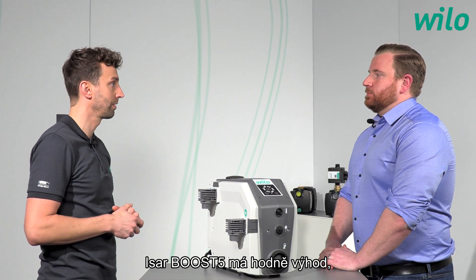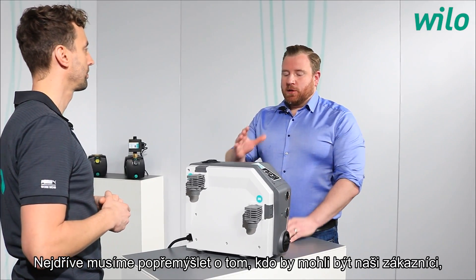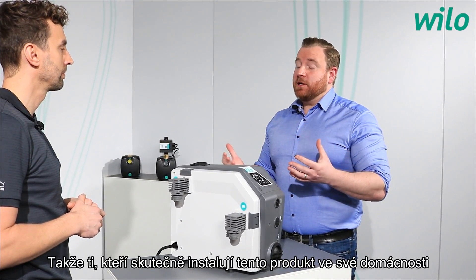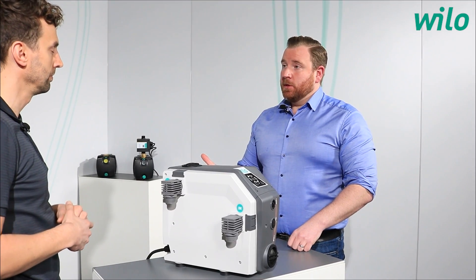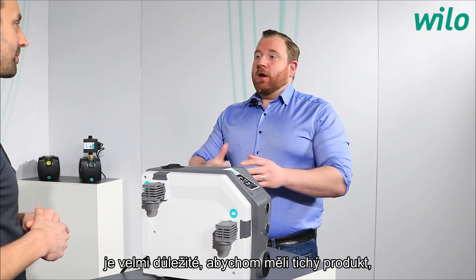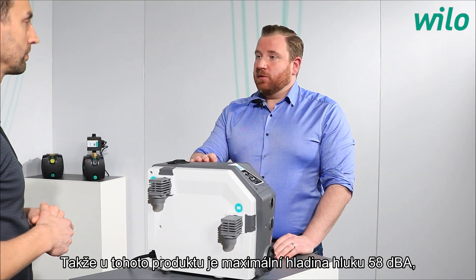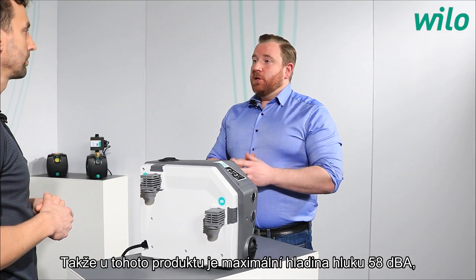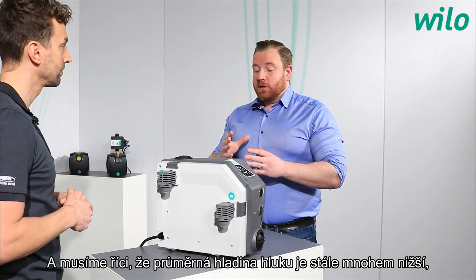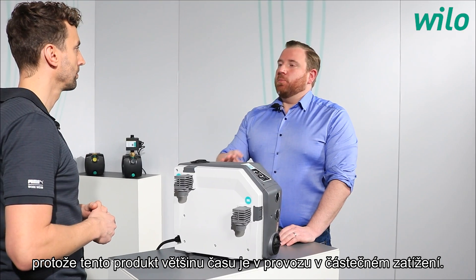The Isar BOOST 5 has many benefits. For end users, silent operation is key — the maximum noise level is 58 dB, which is already quieter than a normal conversation. The average noise level is even lower because the product operates in partial load most of the time. Partial load also means energy savings compared to traditional fixed-speed pumps, as only the hydraulic performance actually demanded is generated.